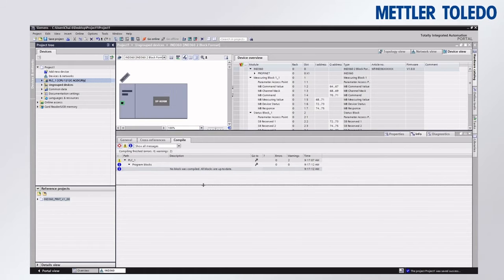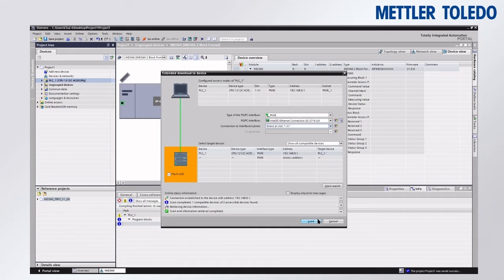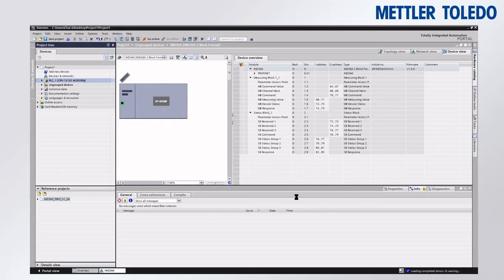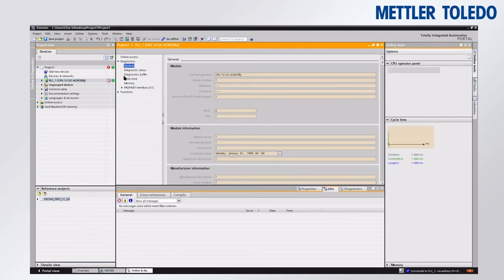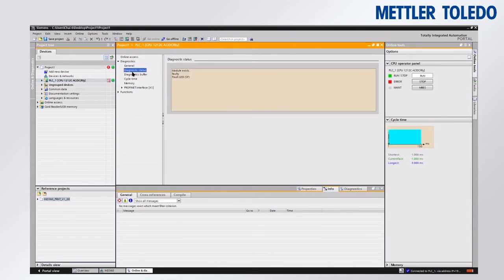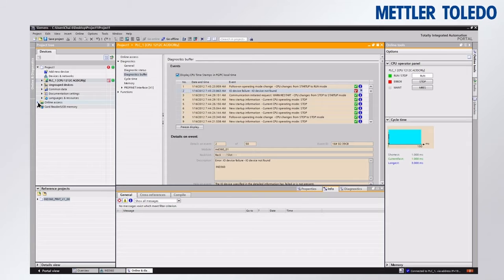When the download completes, I would expect to see some errors, because while we told the project what IP address and device name to expect for the IND360, we did not actually assign those to the IND360 yet. We can see here we do have some errors as expected, and looking at the exact error we can see that an IO device is not found, as we would expect.